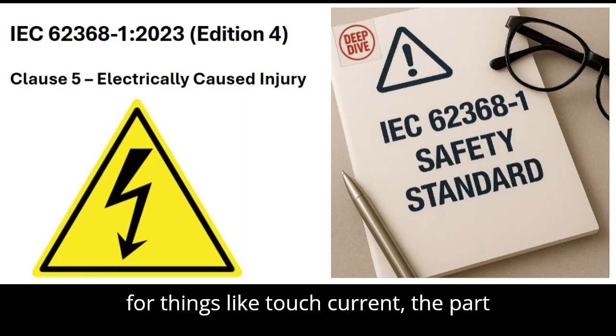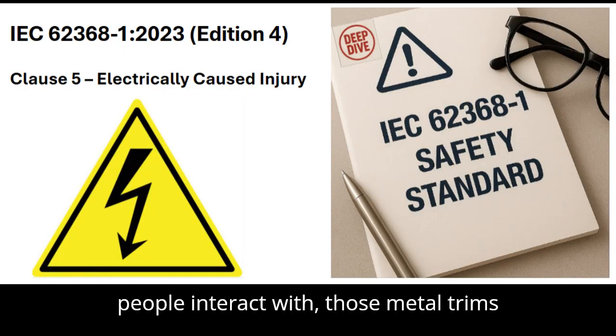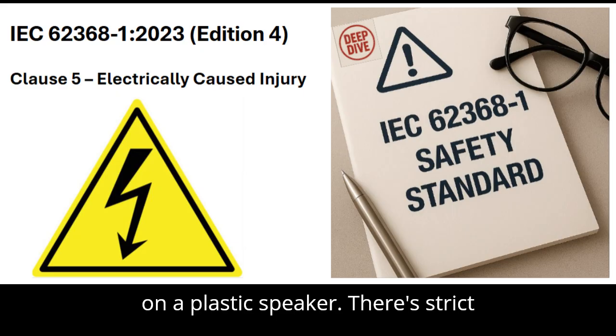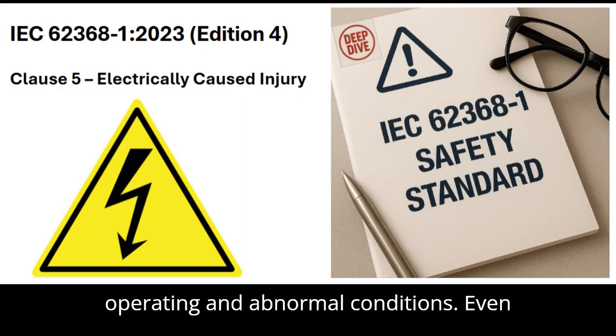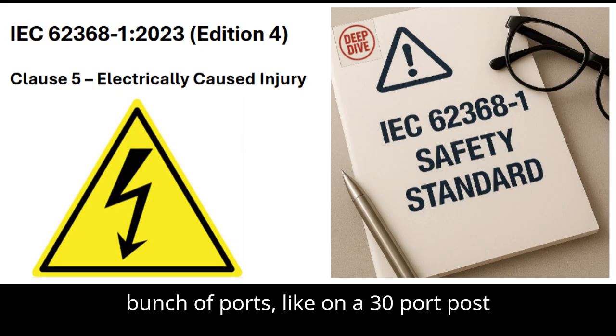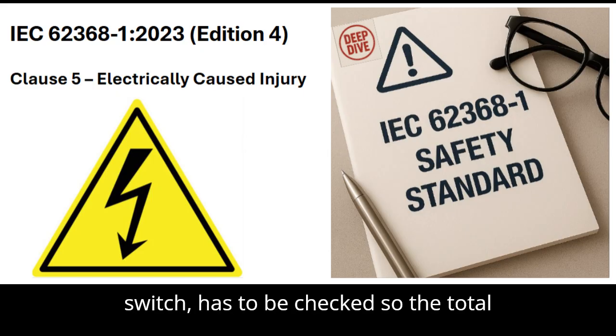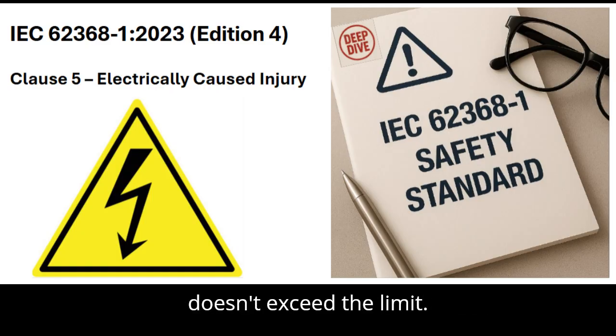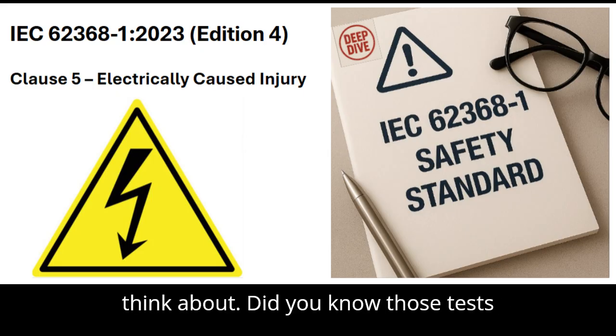And for things like touch current, the part people interact with, those metal trims on a plastic speaker, there's strict measurement for leakage under all operating and abnormal conditions. Even the summation of touch currents from a bunch of ports, like on a 30-port PoE switch, has to be checked so the total doesn't exceed the limit. That's something I bet most people never think about.